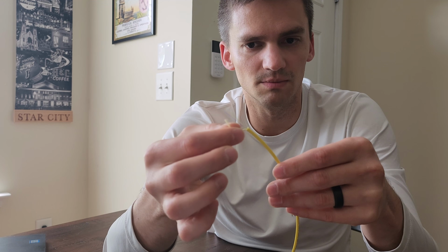But the safety when it comes to fiber makes it more difficult and you have to be more careful. You have to have a good, clean workspace, that whole thing. And you also have to be careful of dust when it comes to fiber. Because these are made of glass, you really have to worry about dust getting on your connectors, getting on the fiber itself. Any sort of scratches on it can really affect the quality of the signal. And so 90% of many fiber issues that we've seen are because of a dusty connector. And so dust control and clean workspace and all that becomes really important.